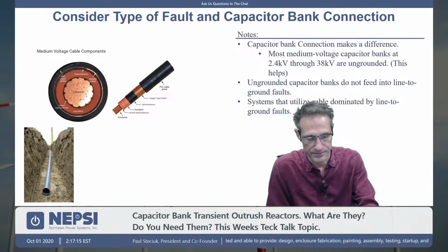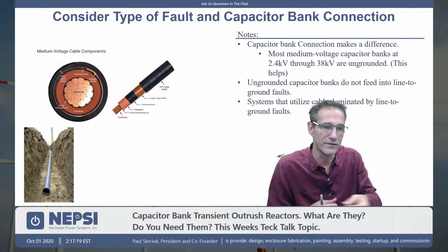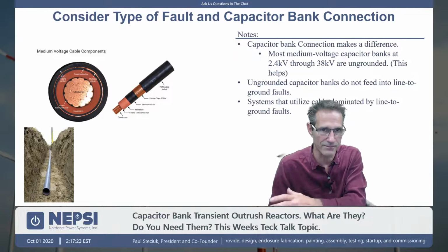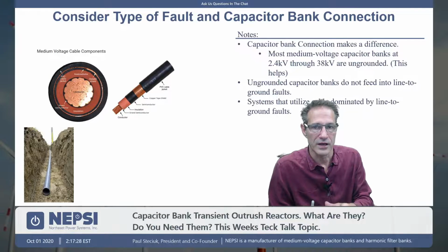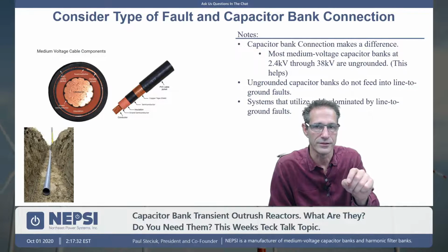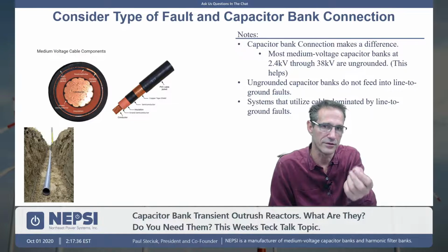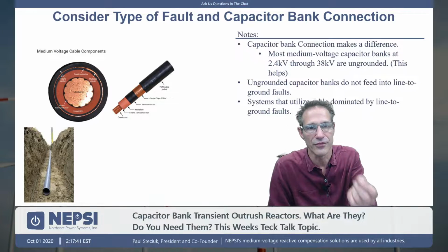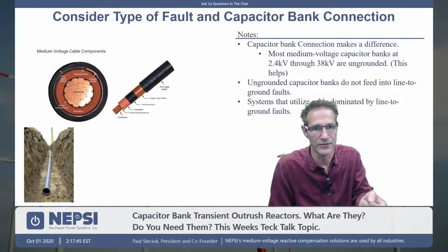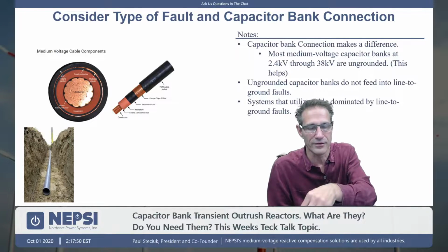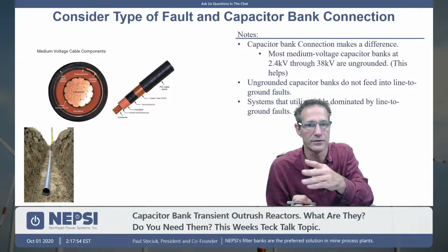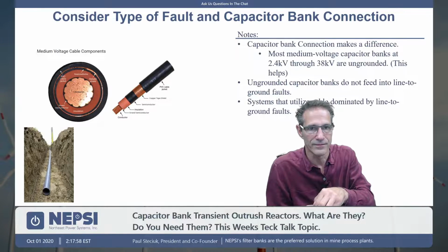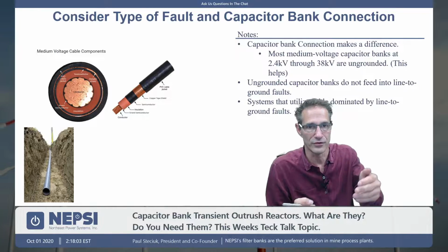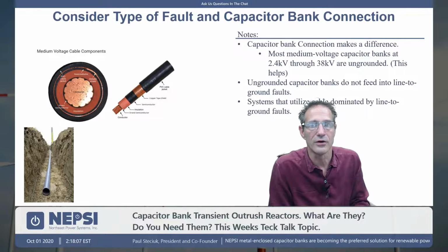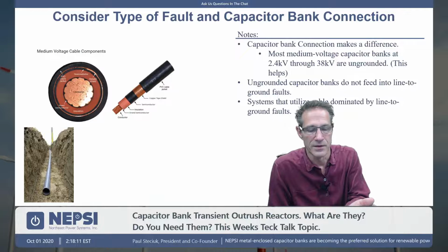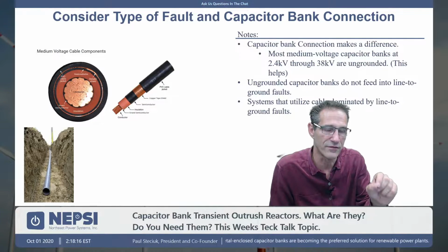If you have a substation that's using cables that leave the substation, so you have your switchgear line up inside the substation, you have your cap bank there. A lot of times when people are doing the transient outrush calculations, they're applying a fault at the breaker inside the substation. If the cables are coming into the substation and connecting to those feeder cables, the possibility of a three-phase fault on that cable is very, very low. Think about a shovel going into a cable, into a ditch like this. It's not going to pass through all 3 cables instantaneously. It's going to pass through 1 cable at a time, right? And therefore, we're going to go line to ground first. That would trip the circuit breaker upstream. It would clear that fault before the shovel got through that second cable. So I think it's an engineering call when you have cables coming into your substation. The amount of inductance that you use in your calculation to the first location of the fault is what matters.